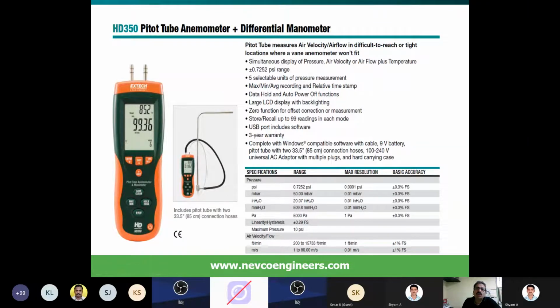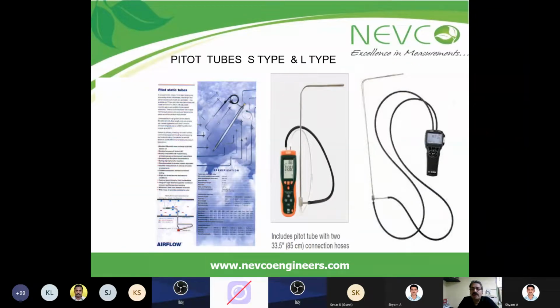In this pitot tube, it will measure the total pressure minus static pressure. You will get a differential pressure, and once you get the differential pressure, then you can very well measure the flow. These are all different pictures. This is all L type. You can see this has 2 ports. Here also you have 2 ports. This is L type, and these are all S type.